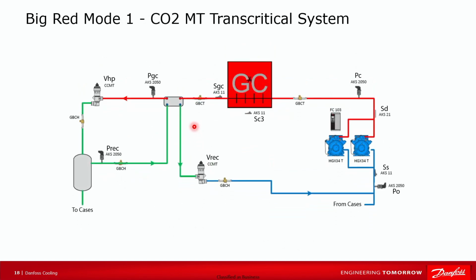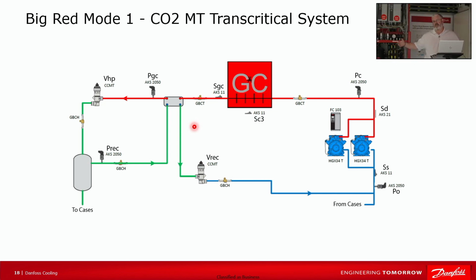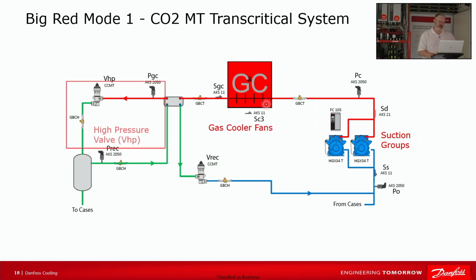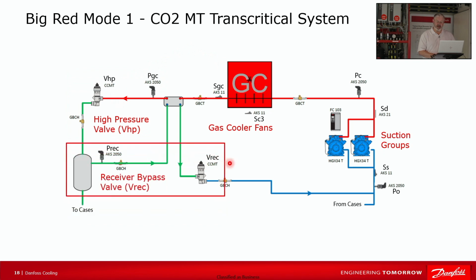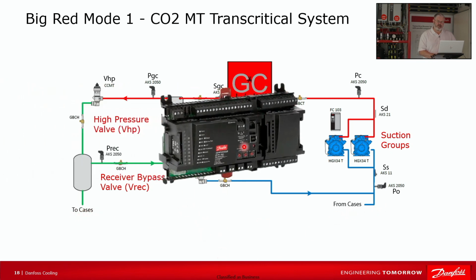So in our mode 1, we're going to go through mode 1, which is just using the medium temp compressors. Then we'll talk about parallel compression. Then we'll talk about ejectors. So in mode 1, we've got 4 basic control areas. We've got the suction groups we need to control. We need to control the fans on the gas cooler. Got to control the high pressure valve as well as the receiver valve. Those are our main components. Here's how we're dealing with return from the evaporators. Here's how we're dealing with the discharge heat of the compressors. Here's how we're getting liquid. And then the receiver valve is dealing with the gas in the flash tank by bringing it back to the medium temp. So we're just going to focus on the high side. I've cut off any cases below or from cases. So again, these are controlled by our wonderful and amazing, powerful pack controller.